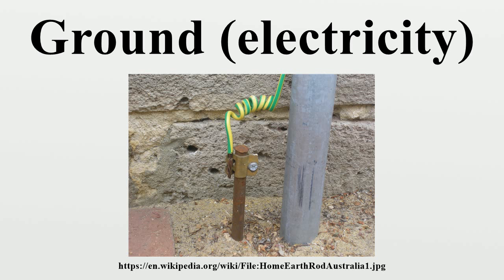Some devices require a connection to the mass of Earth to function correctly, as distinct from any purely protective role. Such a connection is known as a functional earth. For example, some long-wavelength antenna structures require a functional earth connection, which generally should not be indiscriminately connected to the supply protective earth. As the introduction of transmitted radio frequencies into the electrical distribution network is both illegal and potentially dangerous.